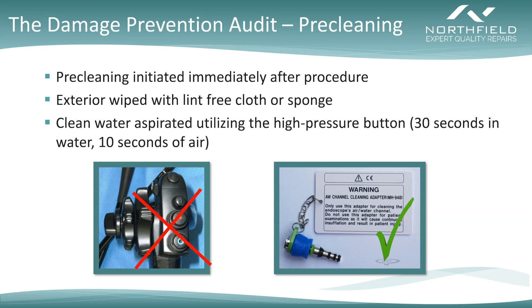For example, if this is after an ERCP procedure, there's separate information specific to that model of scope. Make sure you know what those specific pre-cleaning instructions are and that you are following them every single time. If you do not, we have seen a number of outbreaks associated with improperly reprocessed scopes. And back to that air water nozzle, anytime you see one clogged, it's almost always caused by poor point-of-use cleaning practices.